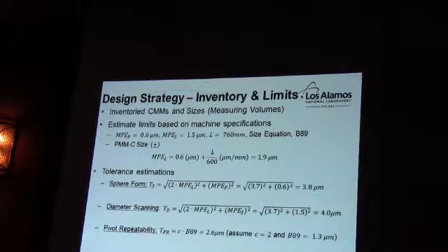It's an outlier. It's telling us something's wrong. Similar for the scanning, the MCG isn't really made for scanning because we have a lot of issues inherent in dynamic scanning that are not the same with tactile probing. But in essence, we're doing the same exact thing, but now we're taking the manufacturing spec for scanning. So anything that's 4 microns.